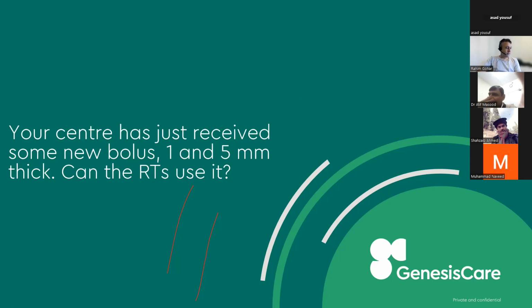So the bolus, we can do the QA simply, check whether it is water equivalent or not. And how will you do that? By placing the bolus on a water phantom or solid water phantom, take the reading and verify it.